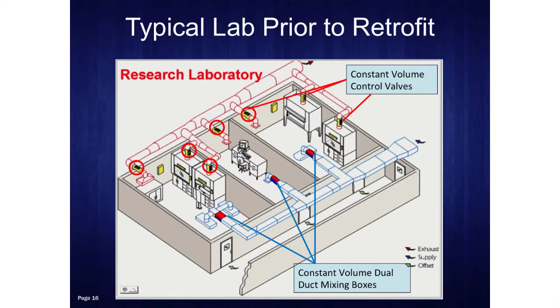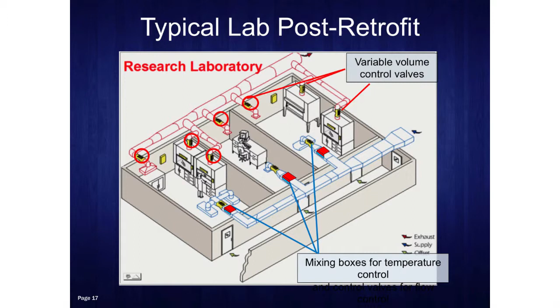So a typical research laboratory prior to retrofit, you start out with your constant volume control valves on your exhaust. Everything is hard balanced. You also have constant volume dual duct mixing boxes. This happens to be a dual duct example, not single duct with reheat. But it's a fairly straightforward retrofit where you're going to change or upgrade those valves to variable volume. You still have your mixing boxes, which are making temperature, but now you have added a control valve to actually make flow.